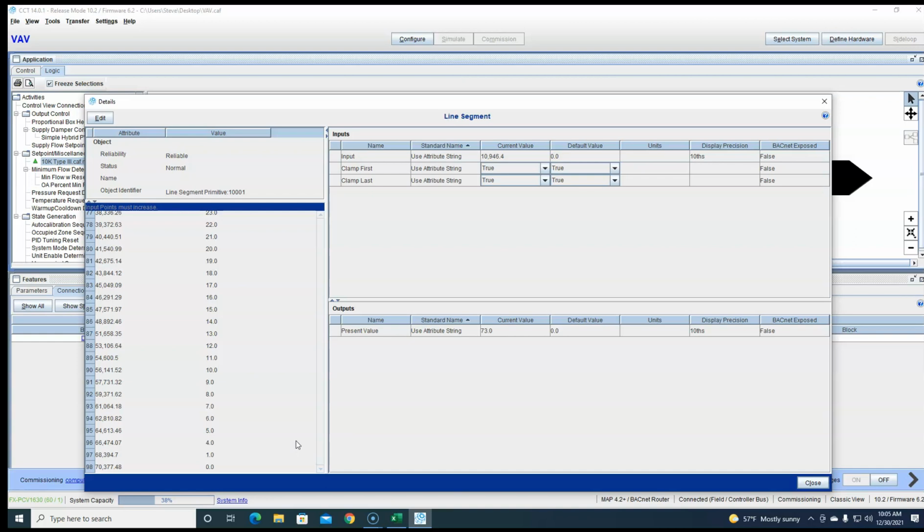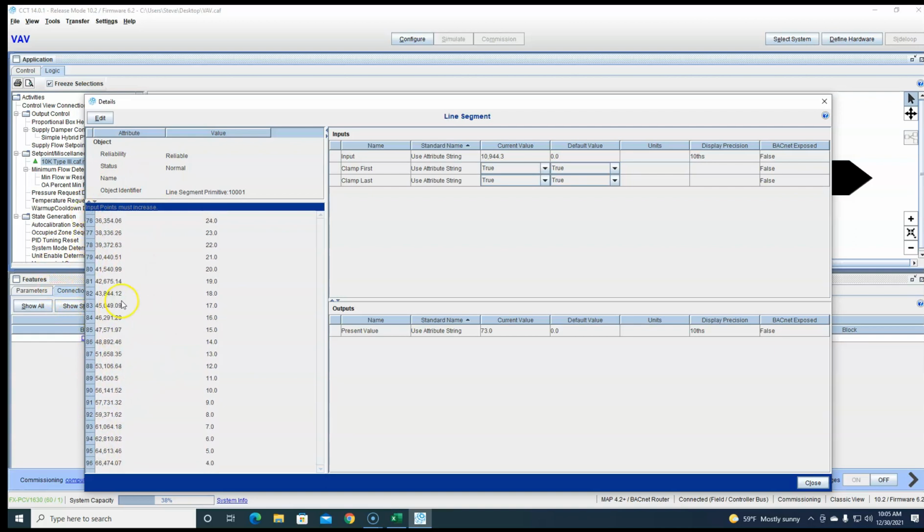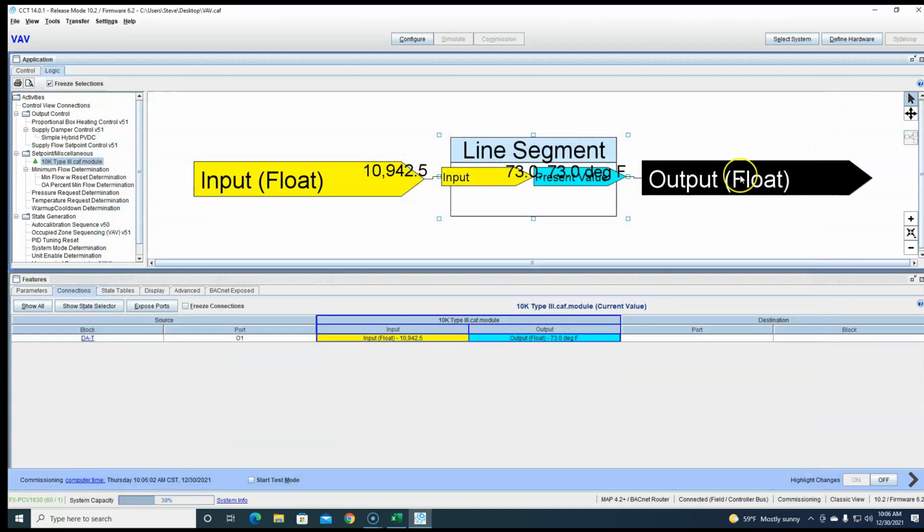So that's when we would need to start doing a little bit higher increments apart, 5 degrees, 2 degrees, whatever we can do to limit the number of columns we have here. They couldn't tell me how many it supports, but obviously it doesn't do the full 301 or 302 degrees to negative 40 degrees. But everything is working here. It's reading 73 degrees. On my desk, it's reading 72.3 on my El Cheapy temperature sensor. So there you go. Now we've got a type 3 thermistor.